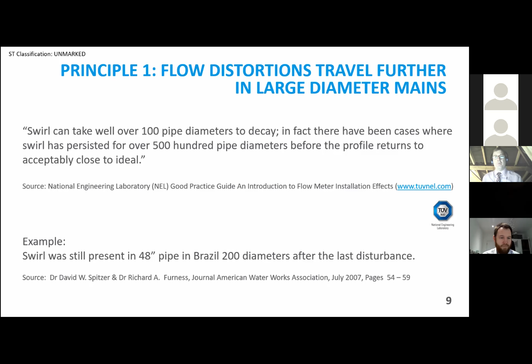Principle 2. For electromagnetic meters, get at least 5 diameters downstream from the last disturbance. A question I often get is, how close to a disturbance can we install a meter? Testing carried out by Evaluation International on a 500mm rig tested an EMAG meter, and put it 0 diameters downstream from the last disturbance. In other words, there was a disturbance, maybe a bend or a partly shut gate valve, and they put the meter directly behind that disturbance. And we see relatively high errors.